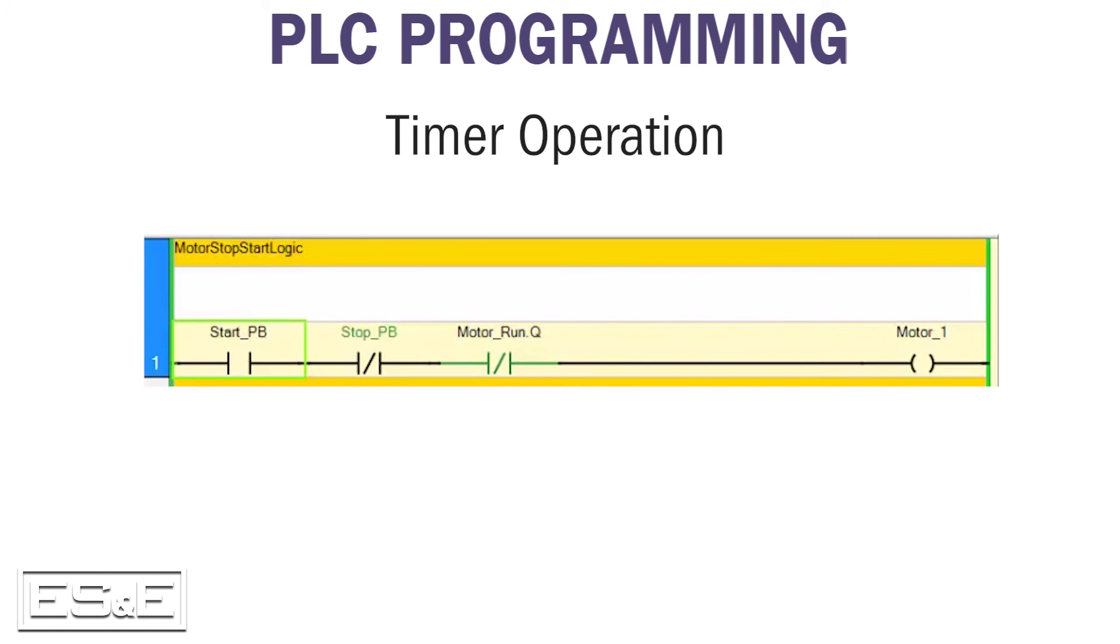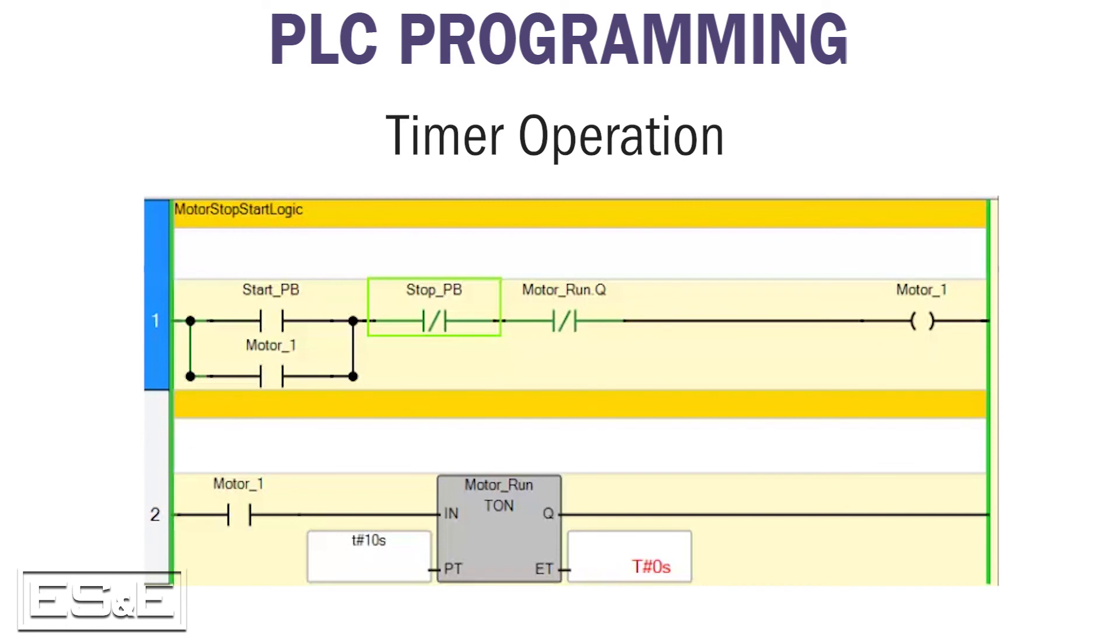Going back to the motor example, when the start push button is pushed, it will solve true because an examine on instruction is used. The stop button is not being pushed, so it will solve true because an examine off instruction is being used. Same with the motor run timer done bit. As long as the timer is not done, the done bit will be true. The rung will solve true and the motor 1 output will turn on. The problem with this logic is that when the start button is released, the motor will stop. To keep the motor running after the start button is released, the motor 1 output bit is used as an examine on instruction in a branch around the start button. The motor 1 bit will be true in the very next program scan after it is turned on. This is known as a sealing circuit.